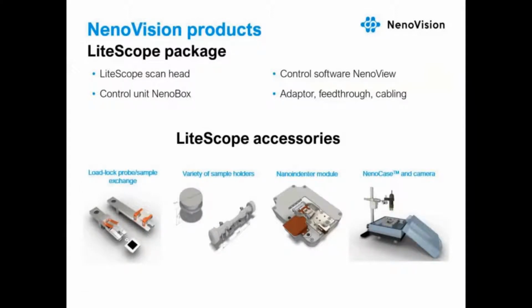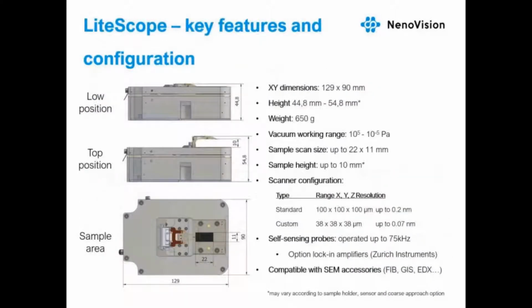In the category of LiteScope accessories, you can find, for example, custom sample holders or variety of tools that are usually developed for specific applications. We also offer AFM probe and sample exchange through a load lock, so you don't have to break the vacuum in the SEM chamber, then a special storage case called NenoCase, which enables you to use LiteScope as a standalone AFM. Lastly, a nano indenter module can be added to the LiteScope in order to combine 3 complementary techniques, AFM and SEM, with nano indentation for advanced characterization of materials' mechanical properties.